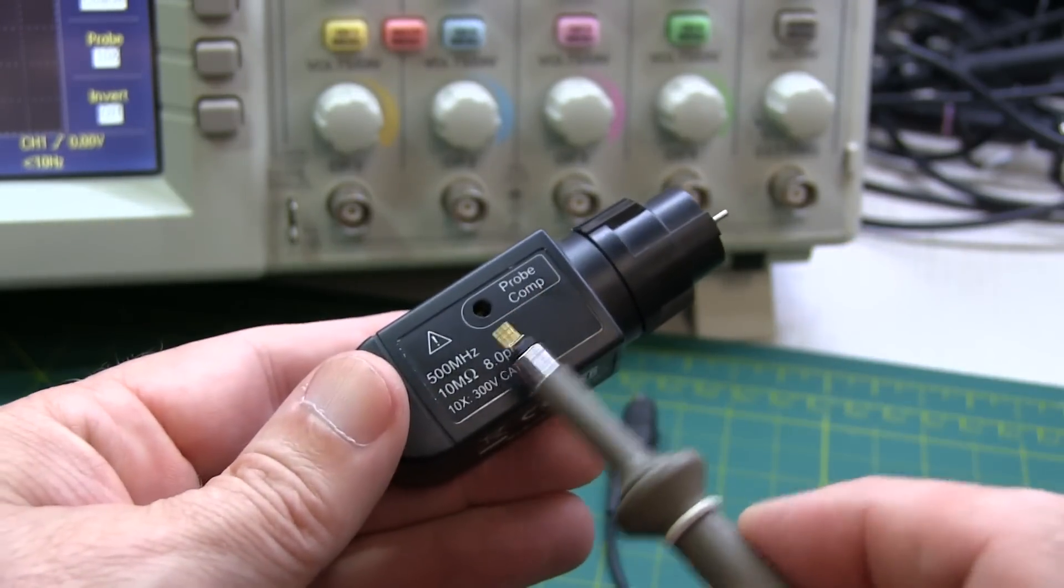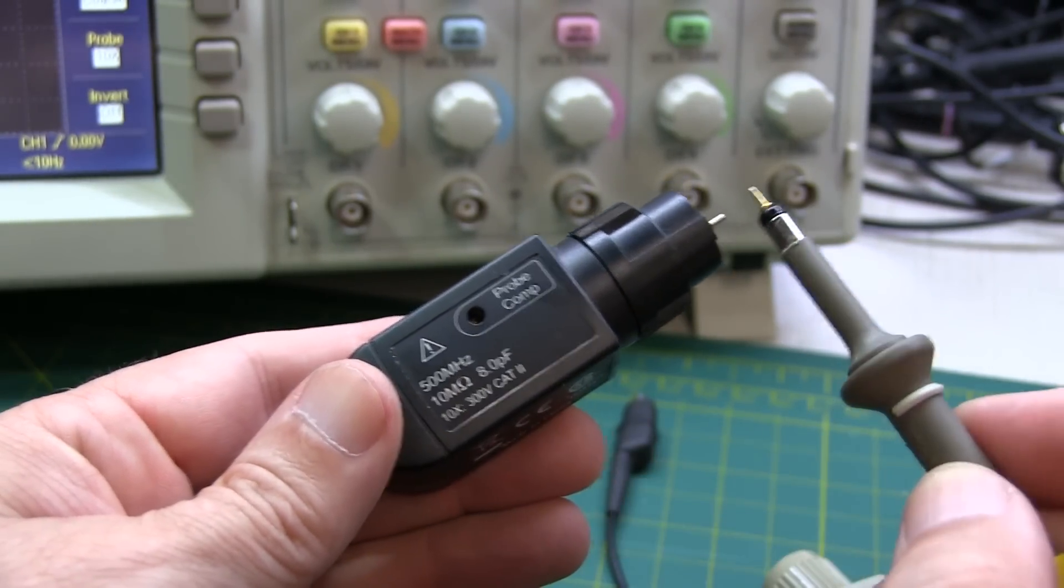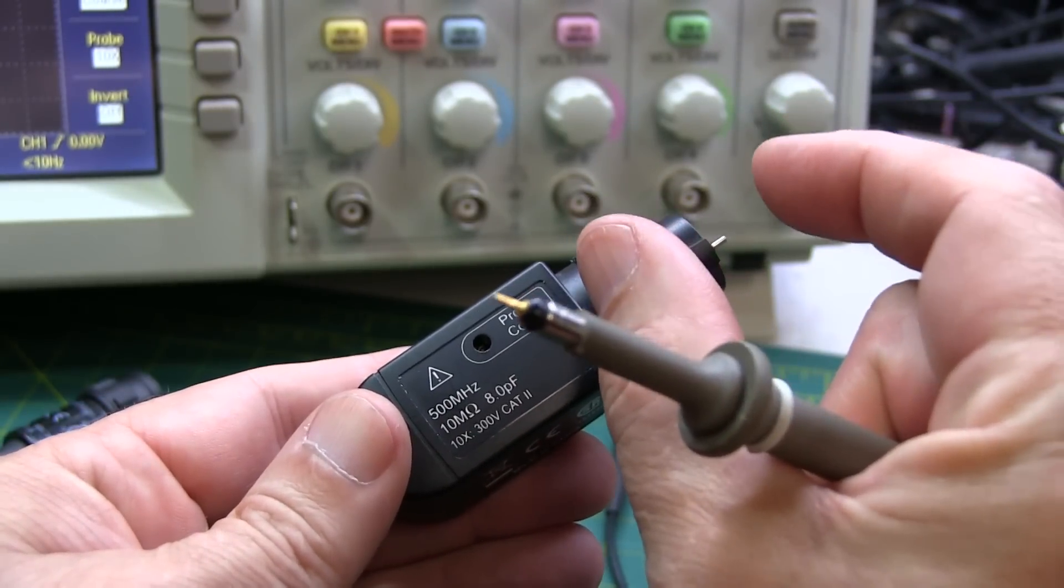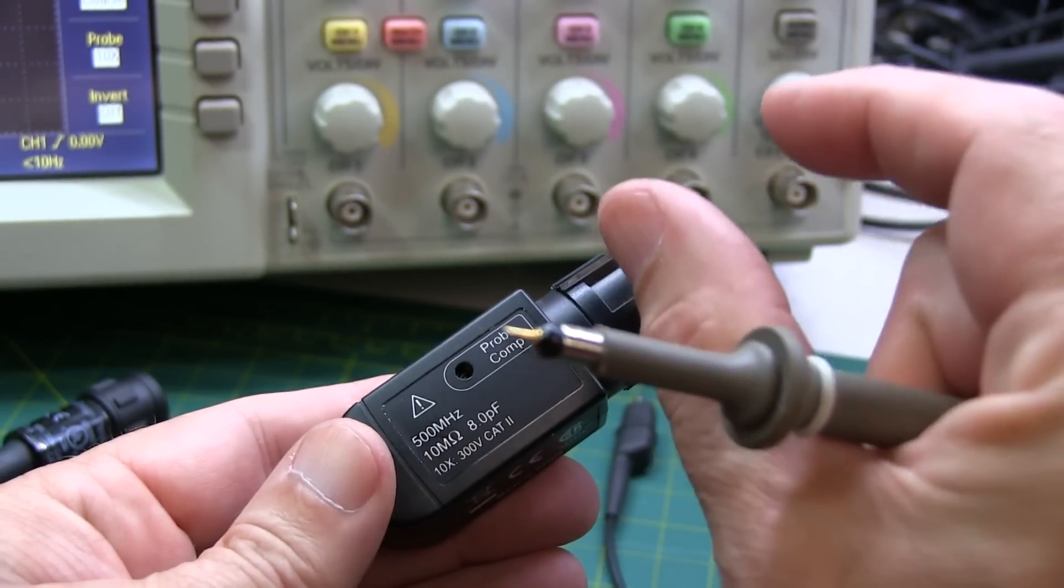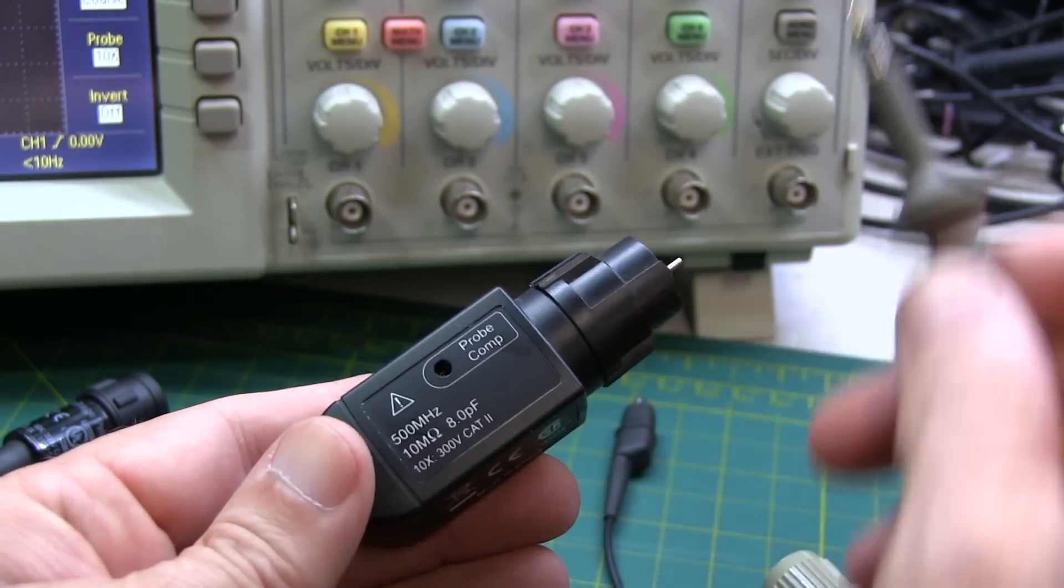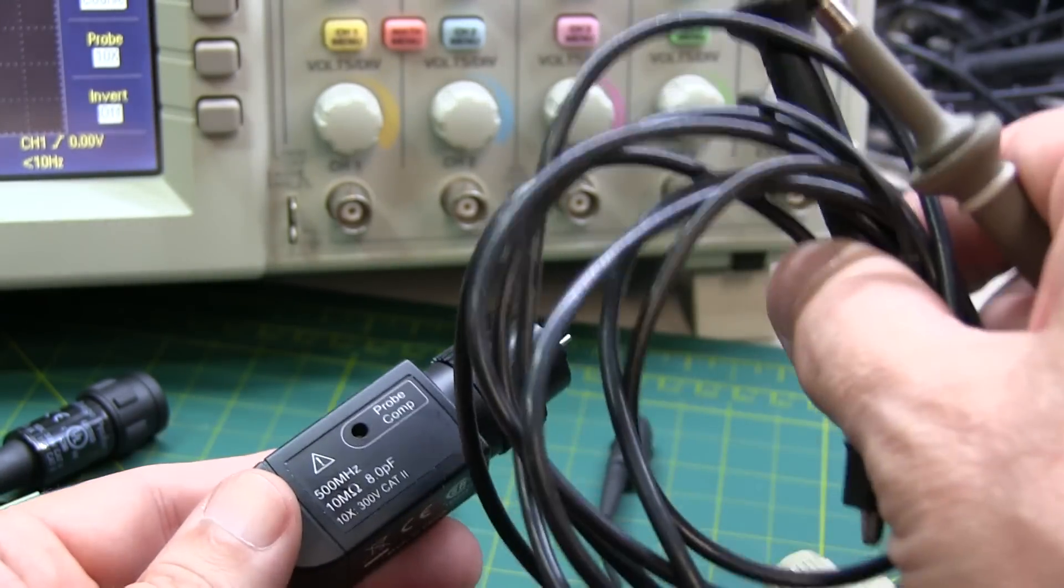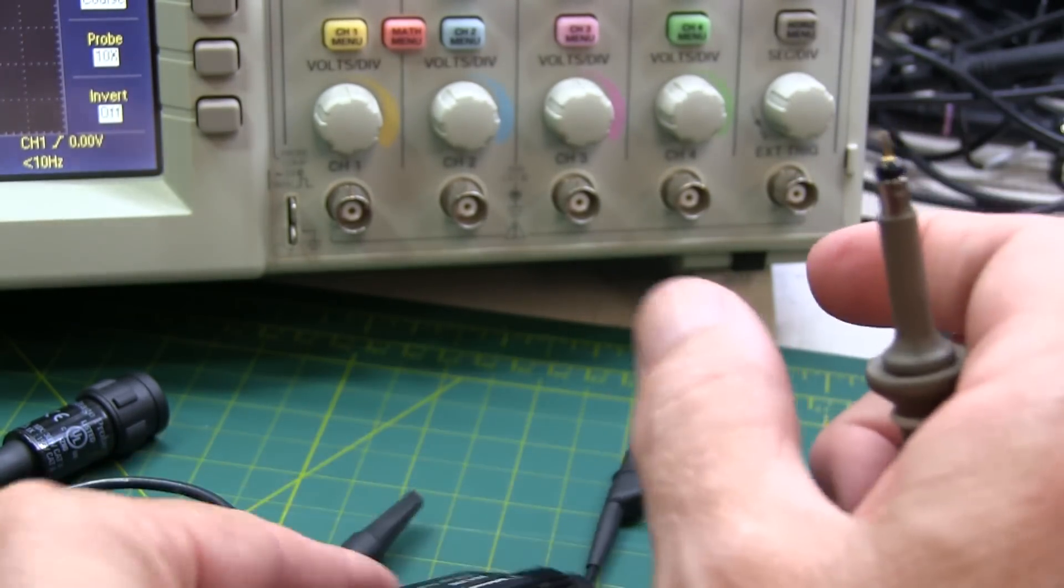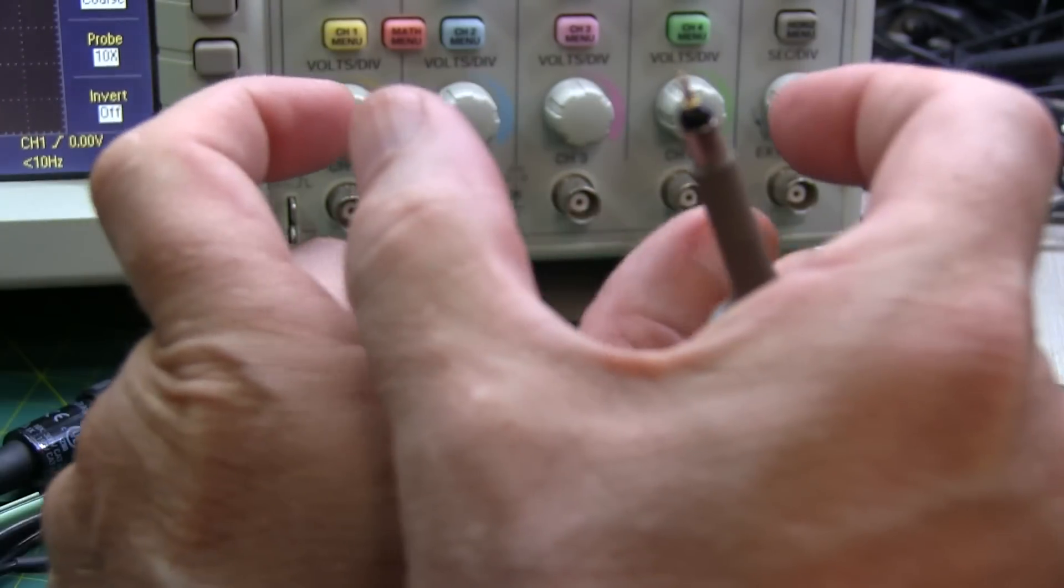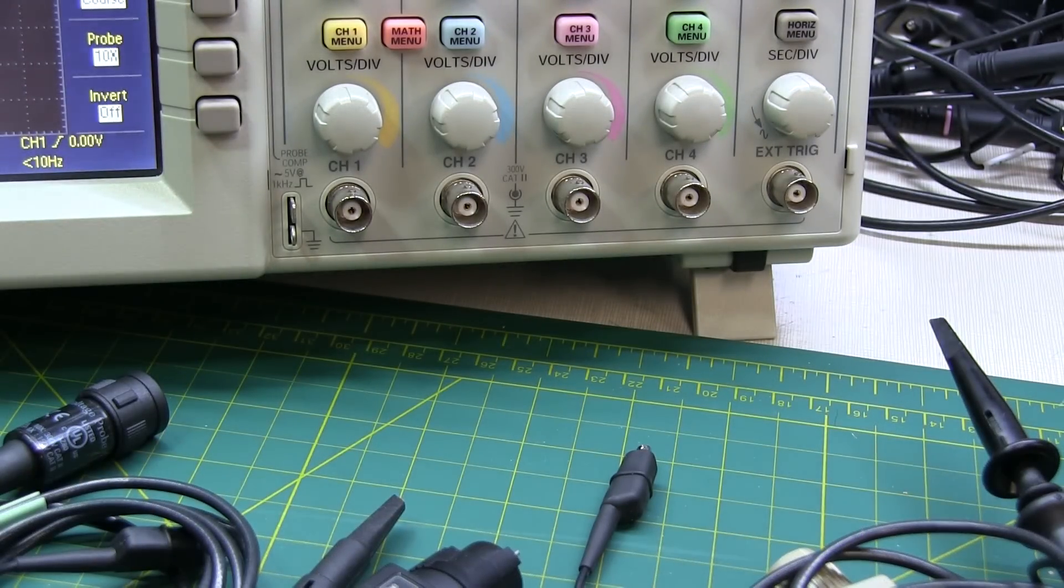Similarly, wider bandwidth probes will have a narrower or smaller compensation range. What that means is a lower range of capacitances that it can be compensated for, whereas the lower speed probes can generally compensate for larger input capacitances. Sometimes they'll overlap, but sometimes those ranges might not overlap. So you do have to take that into consideration.